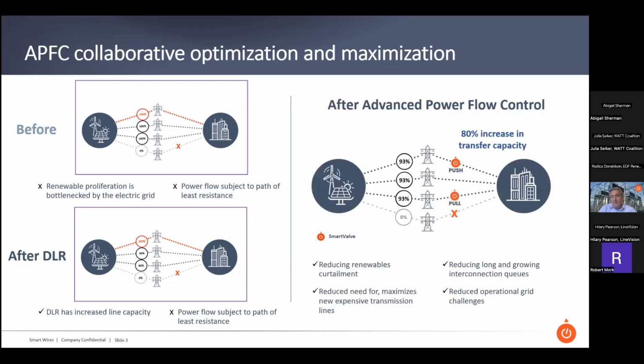If you then combine that with advanced power flow control, you can rebalance the lines, use the capacity there, and by combining the two technologies you get the same type of benefits. You have a wider number of use cases, and as a direct result you've got a greater transfer capability than we saw in the first example.